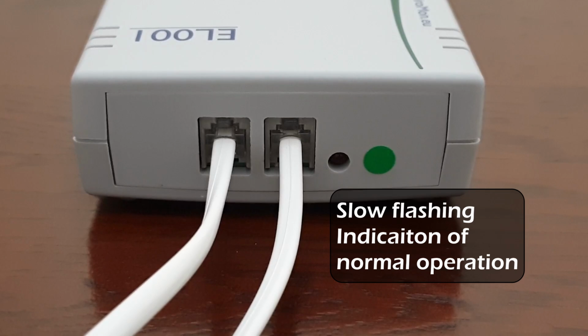One way of telling if the EnviroMon network cable is having a problem is by looking at the LEDs on the converters. The LED should be flashing every now and then, as you can see here.